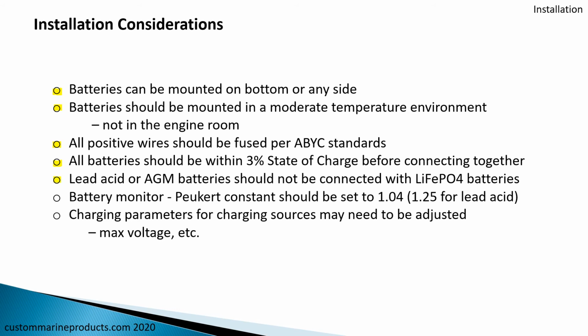Now, we're also often asked the question, can I combine my lead acid with my lithium iron phosphate? And the answer is no. The reason goes back to the performance of these batteries. They charge in a different fashion and they discharge in a different fashion. So while they're compatible with the chargers and they have their own discharge performance, they're not compatible to be wired together. They're quite different. If you have a battery monitor on board, which means you would have a shunt somewhere where the negative of the battery goes into the shunt, and then on the other side of the shunt are your charging systems and your house draw.